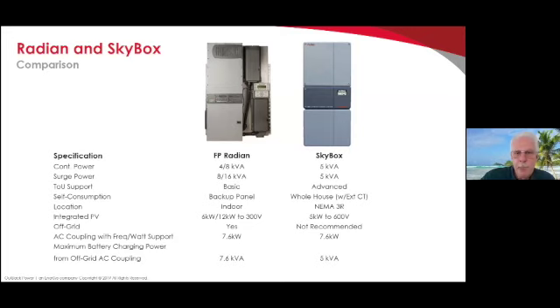And if the grid dependent inverter is a UL 1741 SA model that has the California Rule 21 code in it, you can put it in that mode, and when you increase the frequency, it will decrease its output. So you can actually regulate the charging on the battery within a few volts. So, yeah, it's just the basic rundown on those. If there are still some questions you have, if you're not familiar with these inverters, you can attend our meeting room after at 3 o'clock.